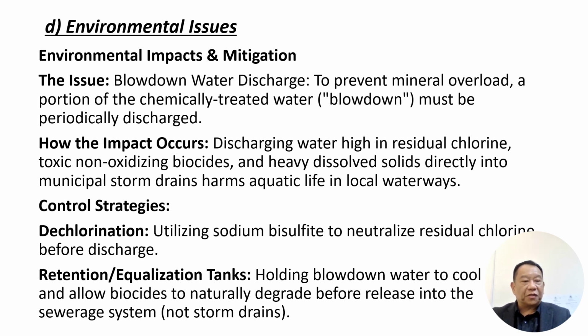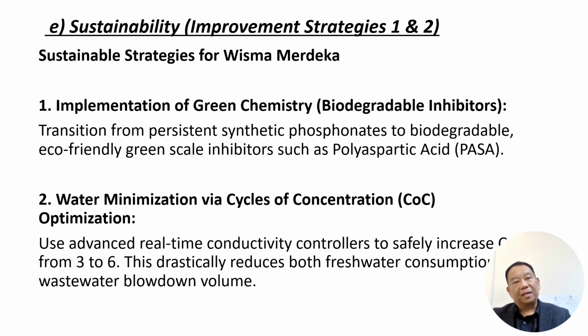And the control strategy is dechlorination, utilizing sodium bisulfite to neutralize the residual chlorine before discharge. And then retention equalization tanks, holding blowdown water to cool and allow the biocide to naturally degrade before release into the sewage system. Okay, so the sustainability improvement strategies 1 and 2 that we have proposed.